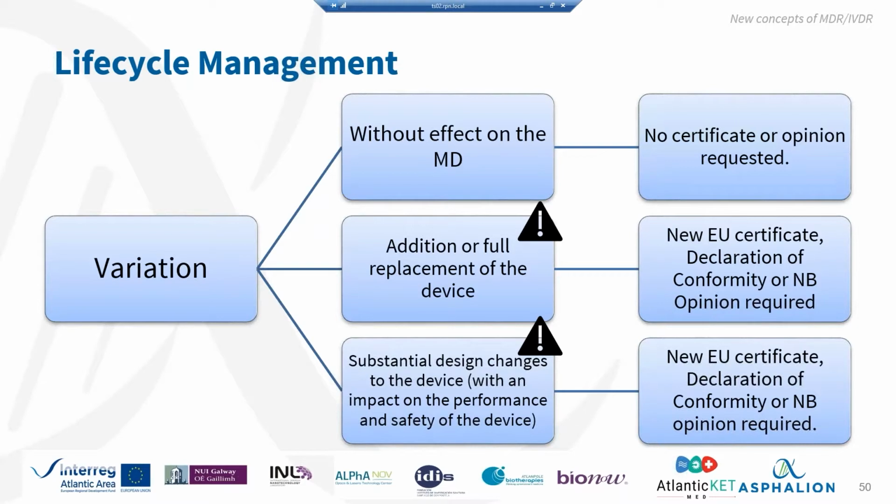Okay, but if a new device is being added, obviously you need to provide a new certificate, or a declaration of conformity, or a notified body opinion. Also, when there are changes that affect this integrally combined device, you also have to provide a new certificate or a new notified body opinion.